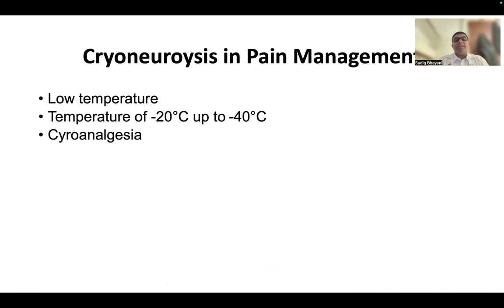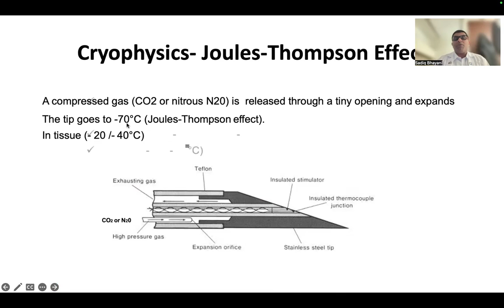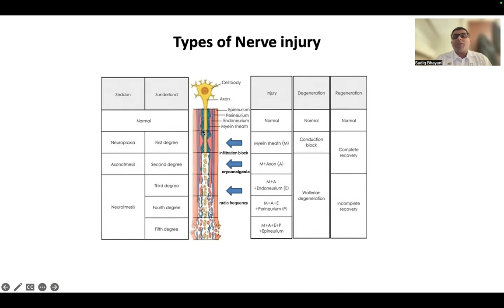And how does it work? It works on the Joule-Thomson effect, the primary FRCA question in physics. When you have a compressed gas that expands at the tip of the needle, it reduces the temperature, and the temperature can go down to -70, but at the tissue level, the temperature will go down to -20 to -40. Now, what it does to the nerve is cause what we call a second degree nerve injury, or axonotmesis. So you're not affecting the nerve architecture, you're only causing axonotmesis. And the beauty is this is completely reversible.